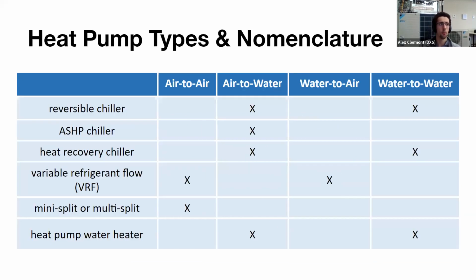Next, we'll talk about some nomenclature before we dive into these heat pumps. A reversible chiller is usually referring to a machine that, again, the word chiller refers to heating and cooling water. So that's usually an air to water machine, or it can also be water to water. You can have a reversible chiller water to water machine. An air source heat pump chiller, as the name implies, heats or cools water, so it's air to water. Heat recovery chillers can be air to water or water to water. VRF, variable refrigerant flow, those are air to air or water to air. Mini splits or multi splits are air to air, whereas heat pump water heaters are air to water or water to water.